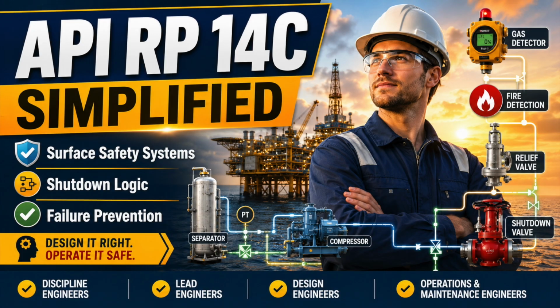Gas blow-by shows why safety analysis must cross equipment boundaries. The separator may survive low level, but high pressure gas can escape through the liquid outlet and overpressure downstream equipment designed for liquid service. The dangerous consequence occurs in another component. The low-level trip therefore protects the connected system, not just the separator. You must understand how much gas can pass, what downstream pressure can develop, whether restrictions limit the flow, and whether the downstream protection can respond in time.